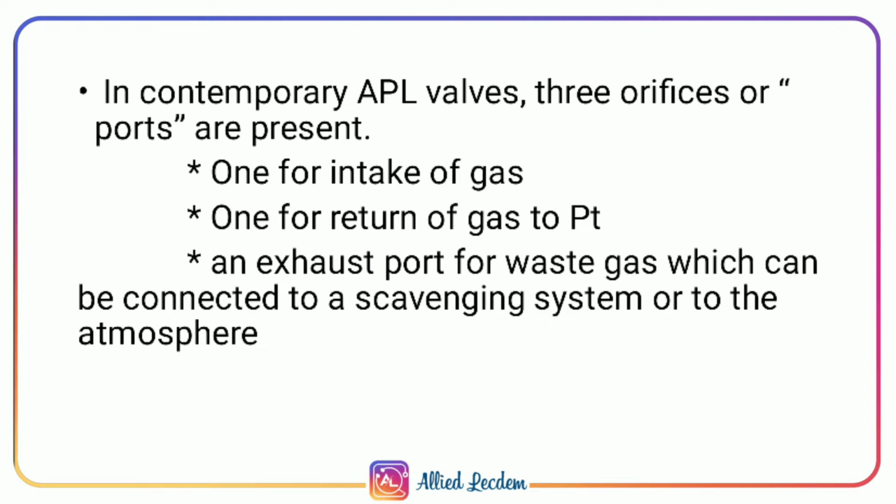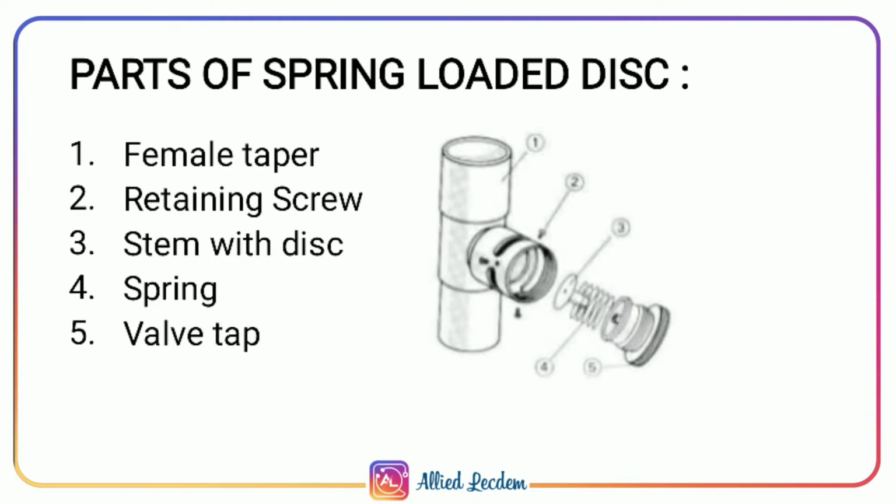One for the intake of gas, second one for the return of gas to the patient, and third, there will be an exhaust port which will collect the waste gases and deliver it to the scavenging system, or it will deliver it into the atmosphere. Parts of spring loaded disc: female taper, retaining screw, stem with disc, spring, valve top.